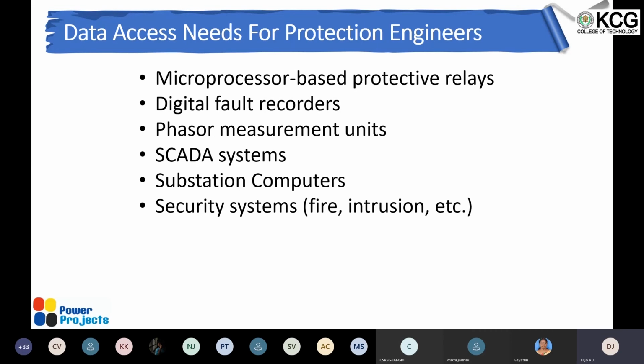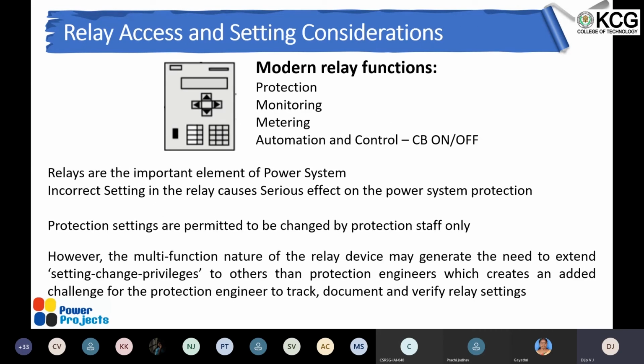So if you take the case of a protection relay, what are the requirements in the protection relay? Nowadays, the protection relay is not just used for protection. Now, most of the time this relay is used for monitoring. Like there will be a direct connection to the SCADA network from the relay to see the status of the system, what is the breaker on/off status, and this relay will also be used for tripping or closing the breaker. So it has more protection functionality, monitoring functionality, metering functionality, and automation and control functionalities also.